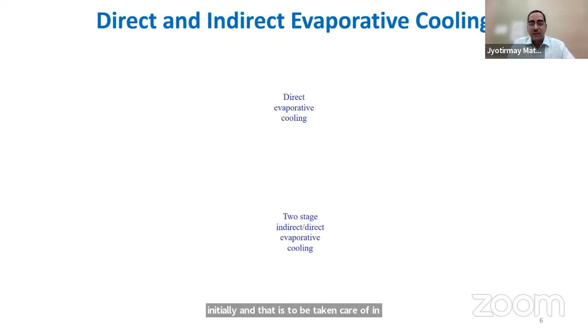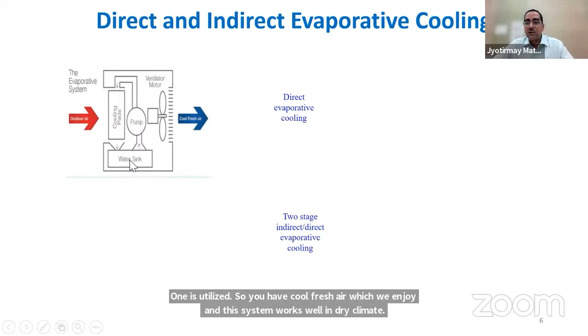Coming to the next point, which has been given to me, is evaporative cooling. There are 2 types of systems in evaporative cooling nowadays. Of course, the principle is that we all have desert coolers in our homes. There is a pad over which water is trickled and air passes over it. Because of evaporation, the heat of the air is absorbed by the water, and the air gets cooled down. The water which evaporates leaves the surface, and therefore the water you get down in the sump is also cool. So you get 2 cooling effects. One is usually ignored, one is utilized. You have cool fresh air which we enjoy, and this system works well in dry climate. But this cool water in the tank is also a good cooling source which is normally ignored.